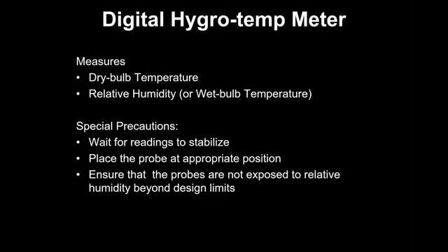Now, the most important thing we have to do is wait for the reading to stabilize, because RH, as I said earlier, also takes a lot of time to stabilize. Otherwise the reading won't be correct. Another problem I have seen extensively is that there is a limit to which the instrument will work, especially on the RH side. Some of the instruments say 95% non-condensing, some of them say 100% non-condensing. So if it is condensing, if you try to measure just at the AHU outlet, sometimes there are some water droplets. They go inside and clog it, and you don't get any reading.